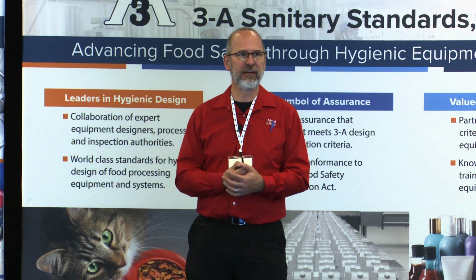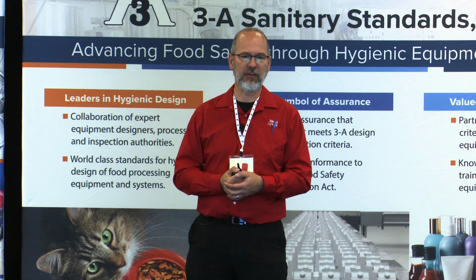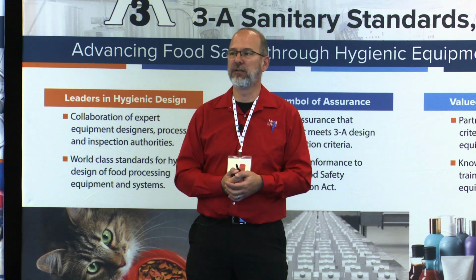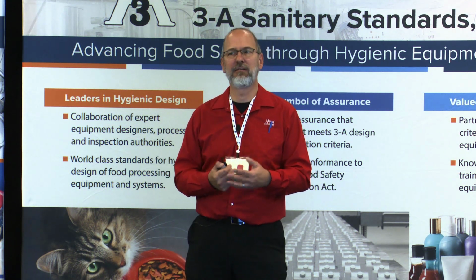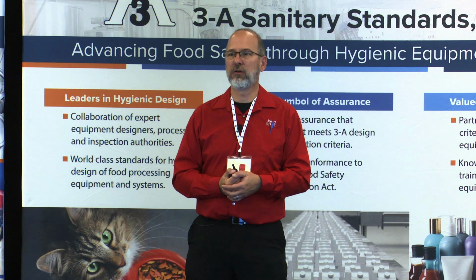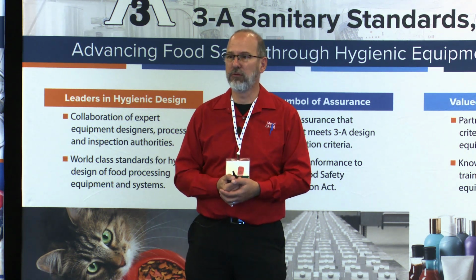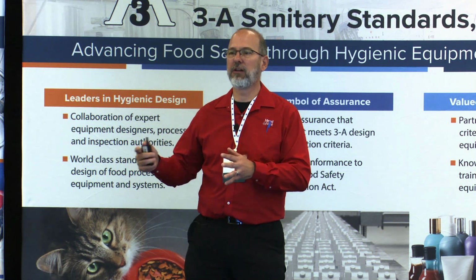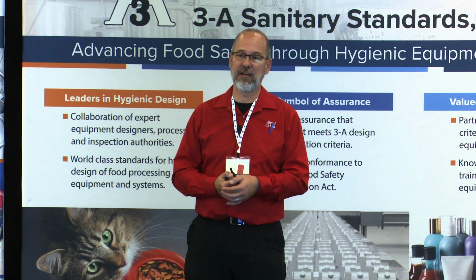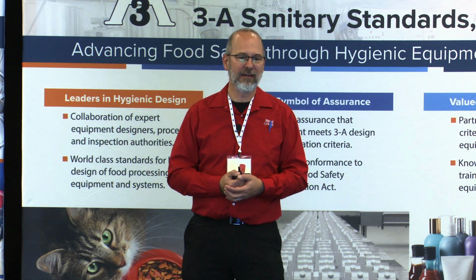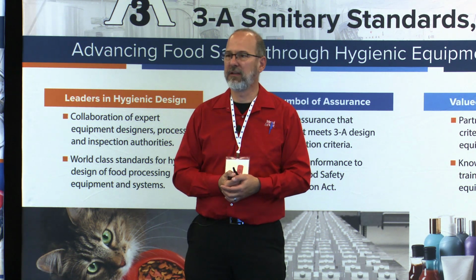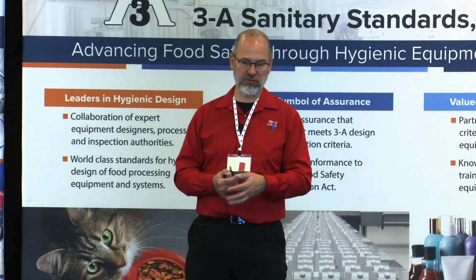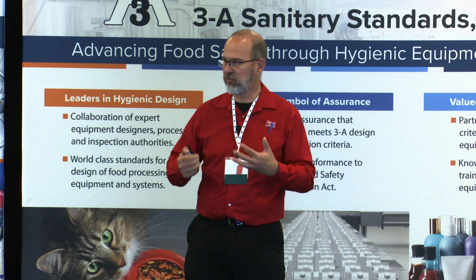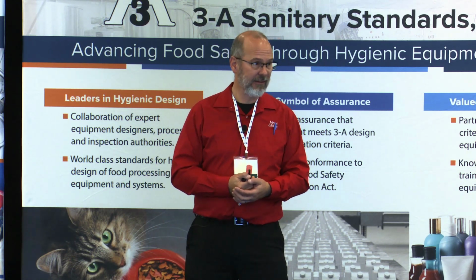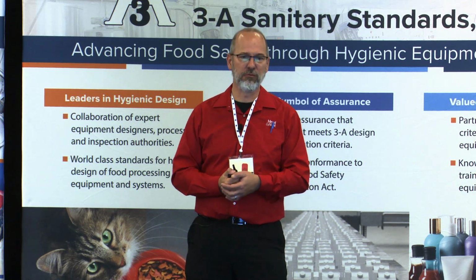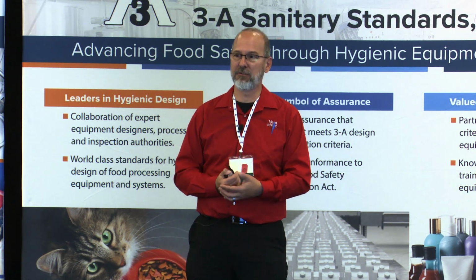Way back when I started engineering HVAC systems, it wasn't uncommon for me to see older plants that just had large makeup air units where they would bring a huge amount of air in, heat it, no cooling, and dump the air in the most critical process room, say a starter room or a vat room in, say, a cheese plant. And then you would just transfer the air to lesser critical rooms and then eventually exhaust it out of the building. So that was single pass air through the building and out. They just moved huge amounts of air, didn't really worry about humidity levels in the space, weren't worried about wet rooms, floors were always wet. It just didn't matter. Well, over time, as we've gotten a better understanding of bacteriology and how that stuff grows in food rooms, we've been working harder and harder over the last couple of decades to dry the rooms out.